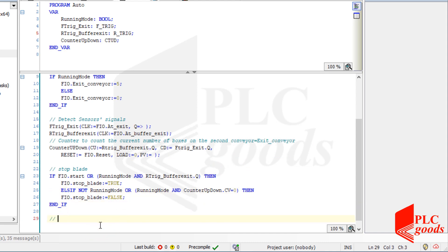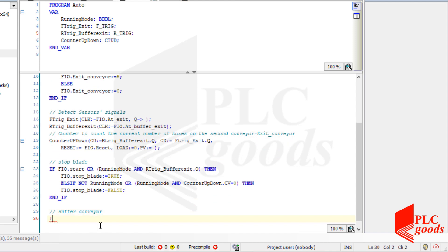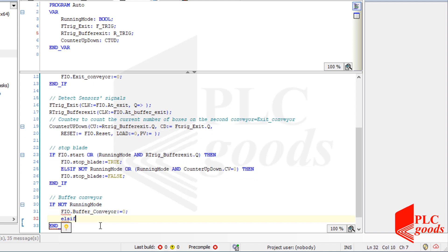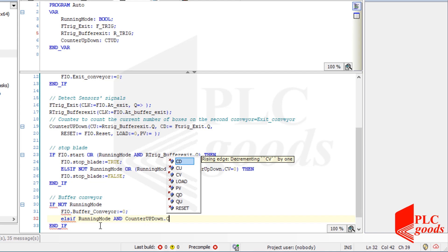Now let's write a program to control the first conveyor, whose name is buffer conveyor. Naturally, when the system is not in running mode then the buffer conveyor must be off. Also, if the system is in running mode and there aren't any boxes on the second conveyor — in other words the counter value is 0 — the buffer conveyor must be on.